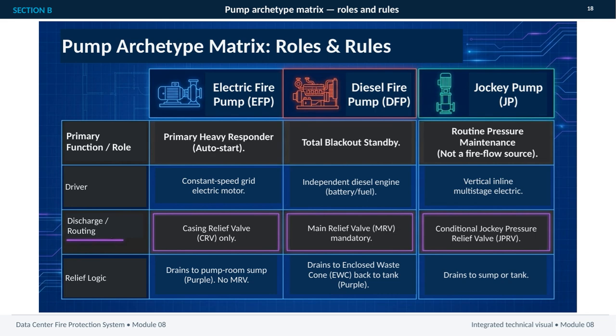It has a conditional jockey pressure relief valve, or JPRV, and its discharge can drain either to the sump or back to the tank. Together, these rules keep each pump aligned with its intended operating condition. They also make clear that relief protection and routing are not interchangeable across the 3 systems.